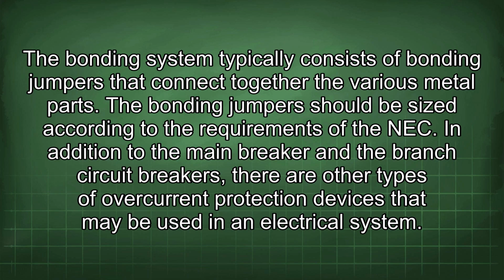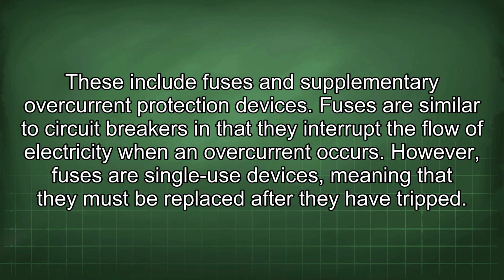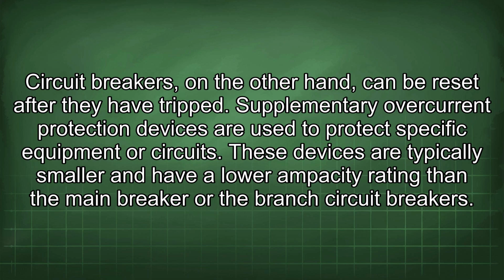In addition to the main breaker and the branch circuit breakers, there are other types of overcurrent protection devices that may be used in an electrical system. These include fuses and supplementary overcurrent protection devices. Fuses are similar to circuit breakers in that they interrupt the flow of electricity when an overcurrent occurs. However, fuses are single-use devices, meaning that they must be replaced after they have tripped. Circuit breakers, on the other hand, can be reset after they have tripped.